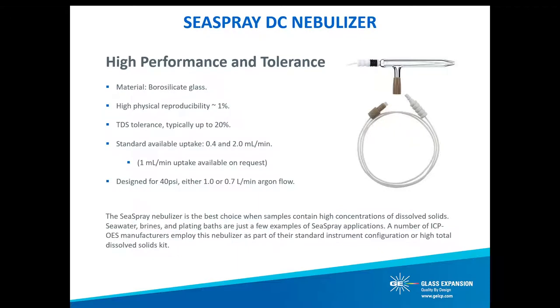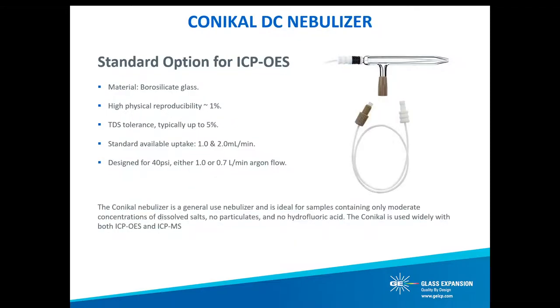The next nebulizer we'll introduce is our Sea Spray nebulizer, which is the best choice for samples containing a high concentration of dissolved solids — sea waters, brine, and plating baths are just a few examples. The unique polished tip of the Sea Spray provides a self-washing design offering freedom from clogging while nebulizing solutions up to 20% total dissolved solids, while at the same time providing excellent efficiency for trace level analysis. The Sea Spray is a standard configuration for many ICP-OES instruments due to its well-rounded overall performance.